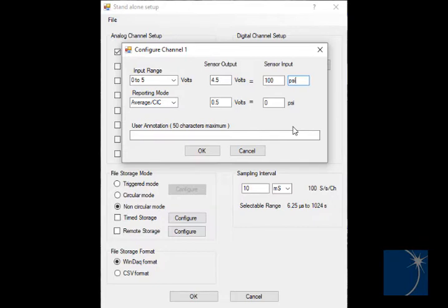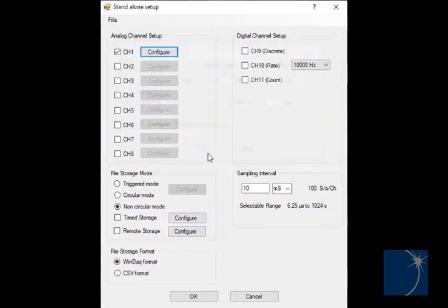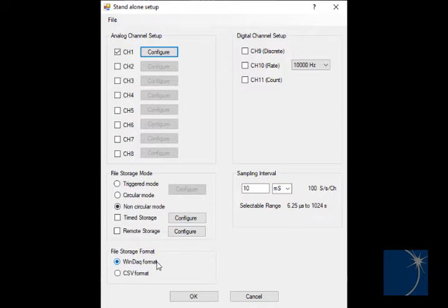We'll change the EU tag to PSI. We'll choose non-circular mode to stop recording when the USB flash drive is full, the WinDaq format to view the data in the browser, and sample the signal at 100 samples a second.